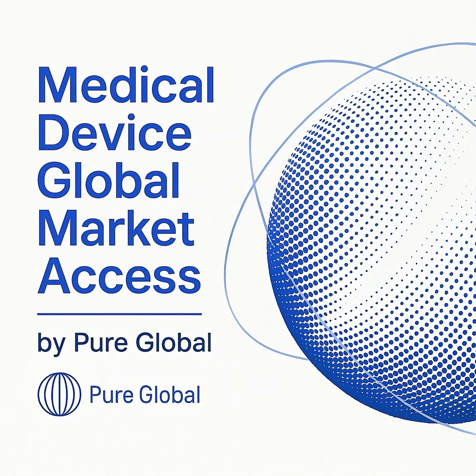Furthermore, the FDA now expects a thorough chemical assessment, including data on extractables and leachables, to identify and quantify any potentially harmful substances that could migrate from the device materials into the blood. This often requires close collaboration with material suppliers to obtain the necessary information, and failure to provide adequate data here is a common reason for review delays.